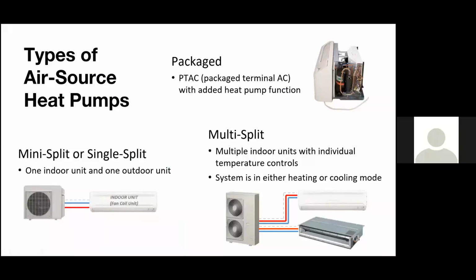So looking at types of air source heat pumps. If you've ever been in a hotel with that loud machine under your window called a PTAC, or package terminal air conditioner, shown in the top right here, it could be a heat pump. Usually in our colder climates, those are just cooling only, and then the heating's done either via electric heat, or sometimes you even have natural gas distributed to all of them. Some do, but some do come in heat pump functions. And in warmer climates, that's really all they use. You can heat and cool with that PTAC. The condenser sits on the outside, evaporator on the inside, and the compressor and the expansion device are all within that little box you can see there in the top right again.